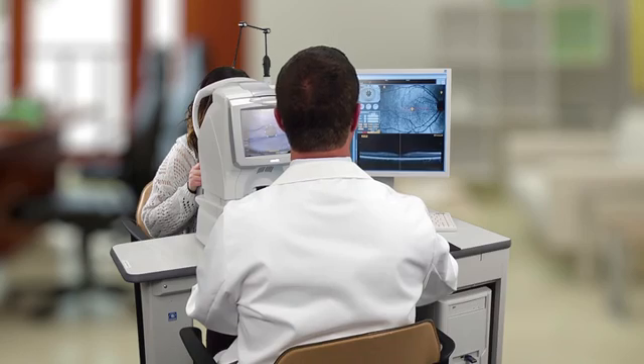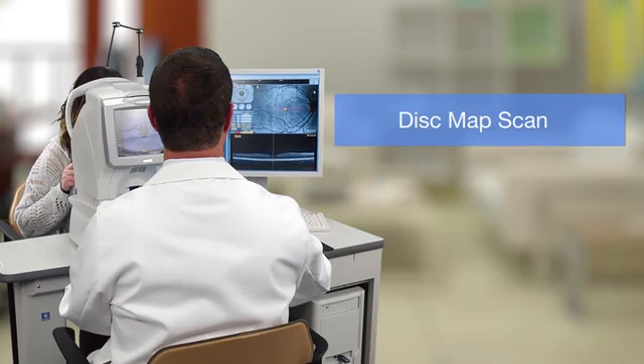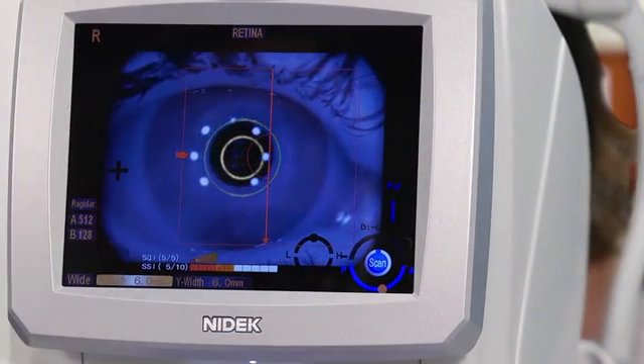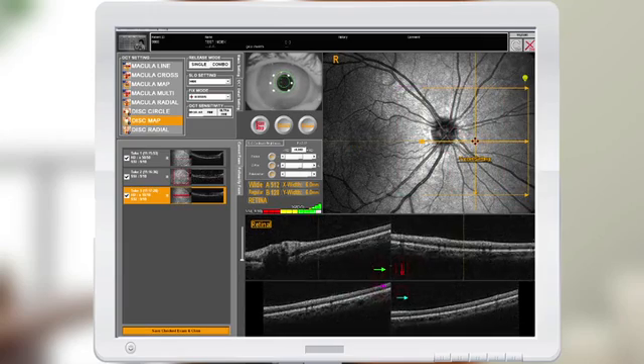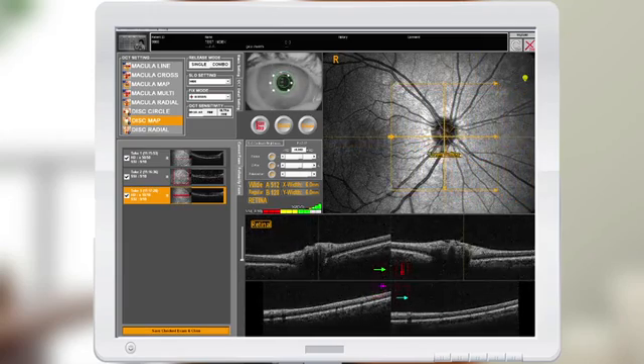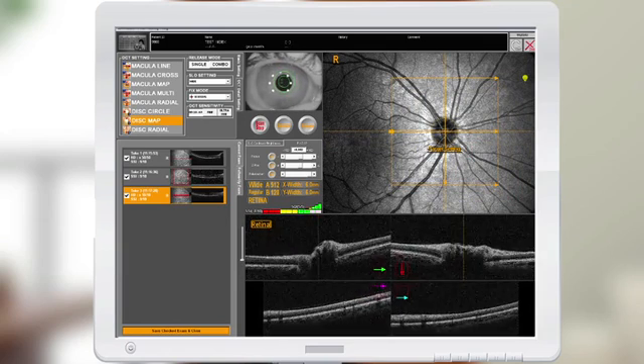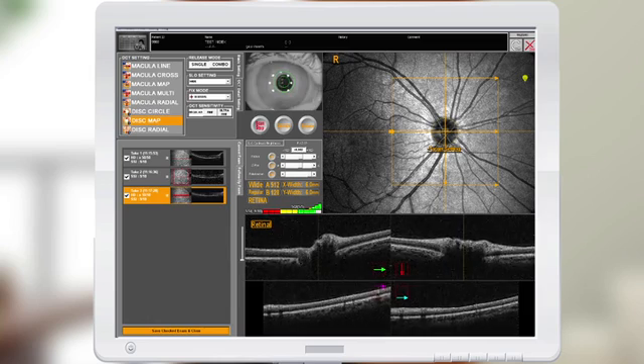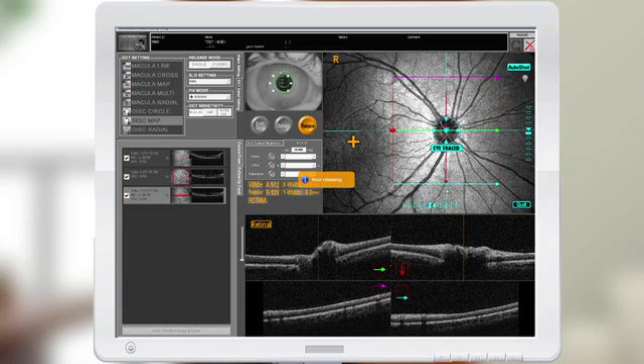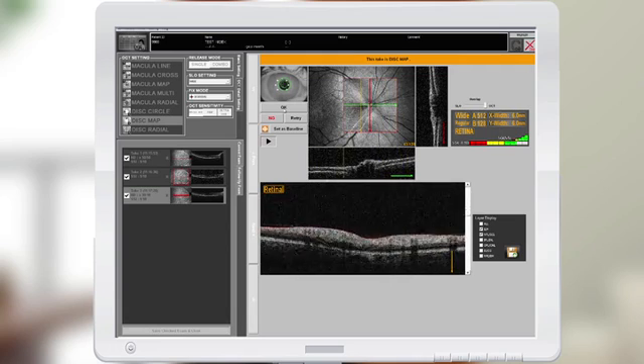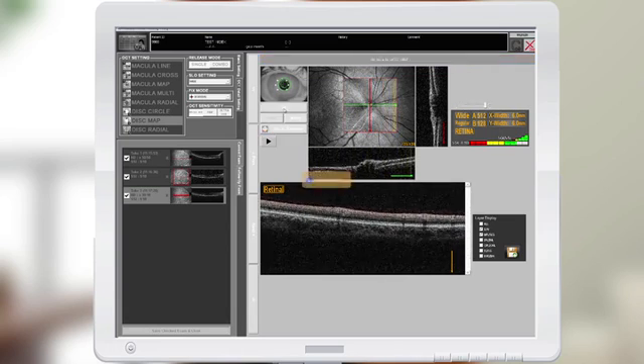I'm now going to demonstrate how to take a disc map scan, which gives you evaluation of the optic nerve head. Left-click and hold on the disc map and align the disc circle to outline the patient's disc. When you drop it in place, the scan will automatically start tracking and scanning. This is our AutoShot feature, which can be turned on or off. Select OK, no good, retry, or set as baseline.